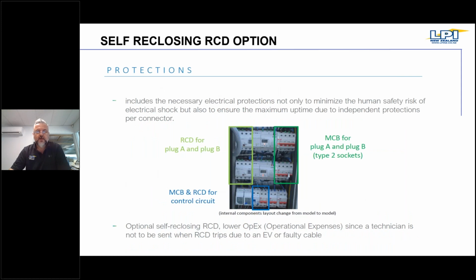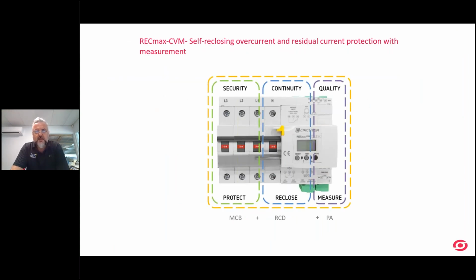Now, one unique option that we can also provide is what is called the self-reclosing RCD option. It might sound a bit scary to some people when they see self-reclosing RCD, but the purpose of this RCD is to constantly monitor and check the state of your installation, and it will self-reclose. It does have a small motor inside the RCD and a breaker. This is sort of like a configuration the way it looks. So it basically has three parts. One is the standard circuit breaker.